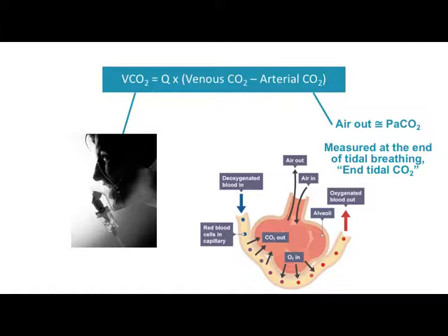Is the problem to calculate the right amount? Yeah. For the second example, it's usually automated, and the metabolic cart will be able to measure breath by breath CO2, and then it fills a bag before you start the measurement with CO2 filled gas. That's meant to approximate the lungs, and then when you breathe that in, it should just clamp diffusion from occurring. We don't have the ability or the technology to do that calculation and fill the bag beforehand. It's too advanced for the equipment that we have.